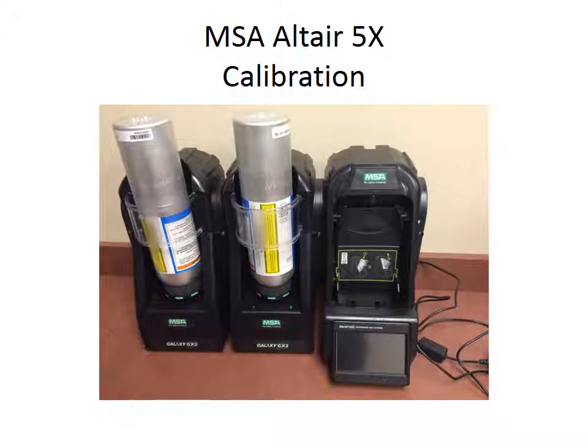Ideally, we want to try to calibrate our meters about once a month. There are different trains of thought on over-calibrating, whether you do it every day, and whether or not that reduces the sensor life of the sensors in the meter. But what we want to try to do is run them through the calibration once a month, maybe 2 months at the most.